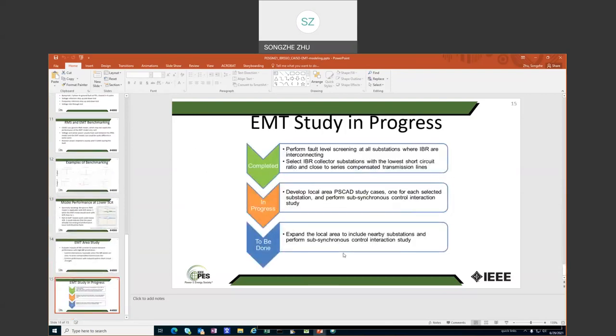So right now our work is in progress. We have analyzed the short circuit strength at different locations in the system. Then we selected the most critical locations for EMT studies. The next step is to develop local area PSCAD study cases for each selected location and perform SSCI study. To achieve this, we must have the EMT models, and that's the current focus.